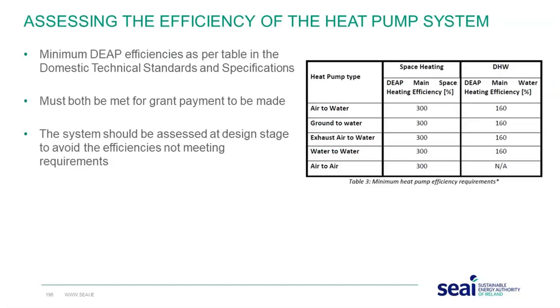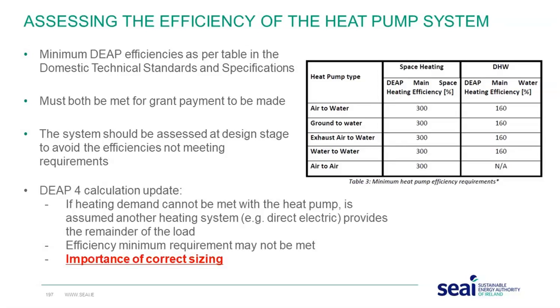Please assess the system at design stage. Please do not do an installation, do your calculations, and find out that you cannot demonstrate that it meets the space heating efficiency or the domestic hot water efficiency. And just an update on the DEAP 4 calculation: if the heating demand cannot be met with the heat pump, so if the heat pump is shown as being less than the overall demand of the house, DEAP will assume that another heating system is being used, for example direct electric, and it will provide the remainder of the load. That will have a negative effect on the overall efficiency because it will bring it down. So this is where, again, I keep saying the same thing, but the importance of correct sizing is essential.